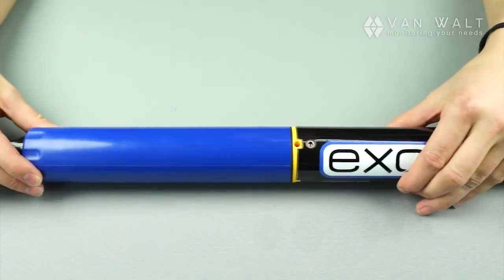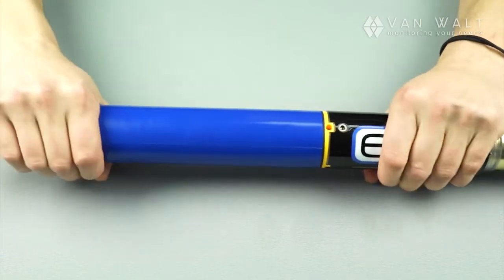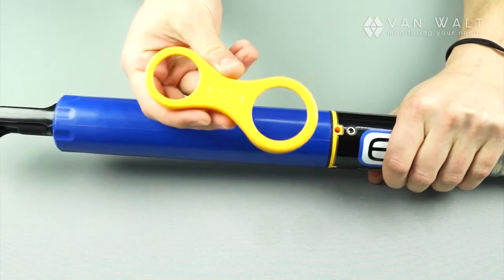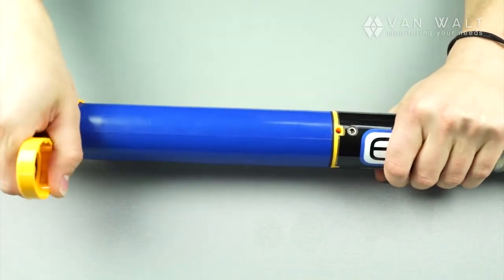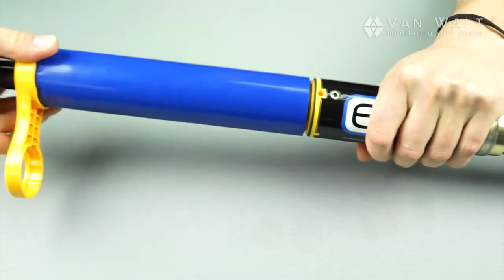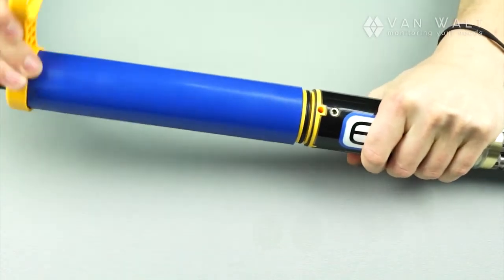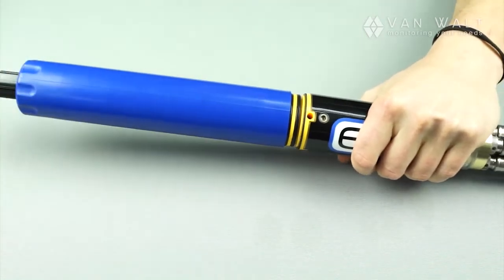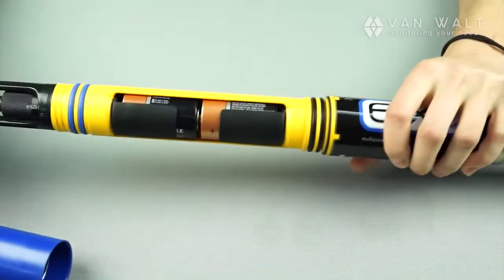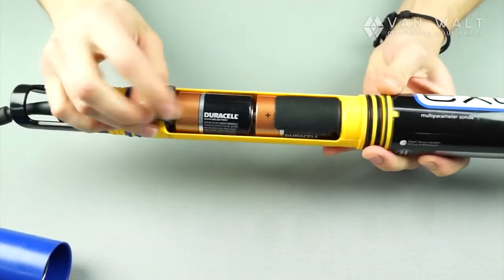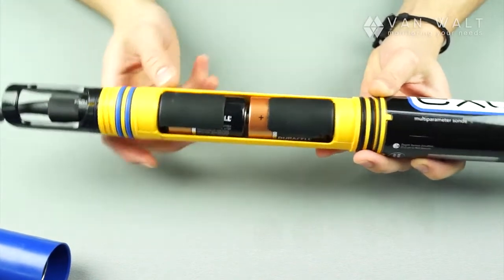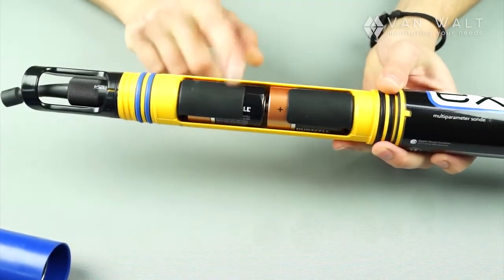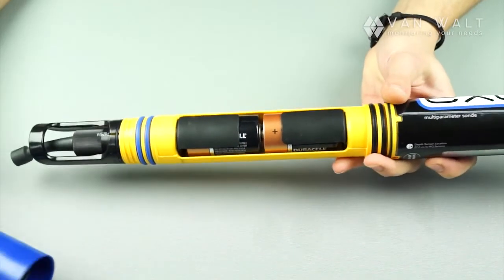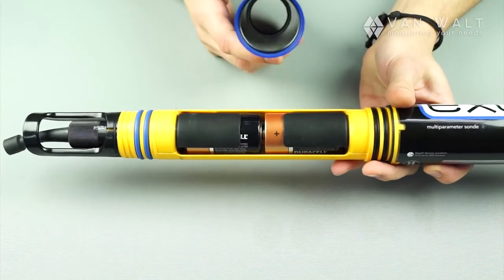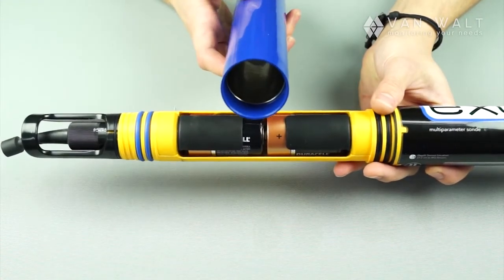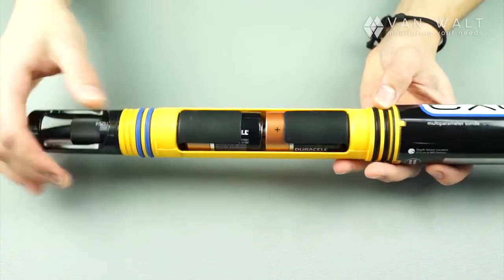The next section of the device is the battery storage. This can actually be done by hand, but they also include this spanner for removing it. Inside here lives two batteries. They have a life of approximately 3 months. 2 size D batteries behind these rubber flaps. When these are replaced in the field, the unit will automatically continue logging after the batteries have been changed, which is pretty handy. They've also lined this housing with stainless so that if needed it can be clamped or held with tooling.